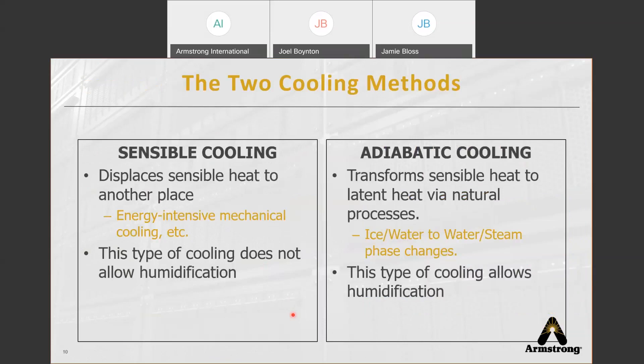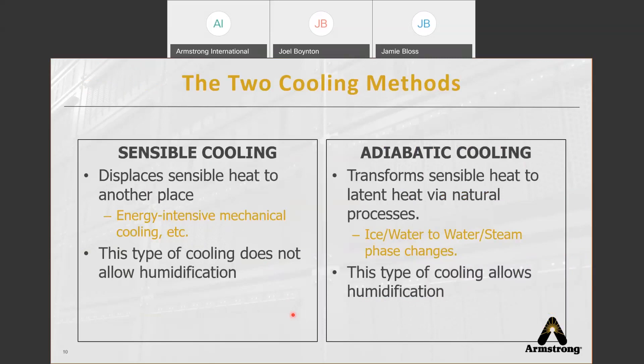That brings us to the two forms of cooling and humidifying in the data center world. These two methods are sensible cooling and adiabatic cooling. Sensible cooling displaces sensible heat to another place — an example is mechanical cooling, which is typically very energy intensive — and this type of cooling does not allow humidification. Contrary to that is adiabatic cooling, which transforms sensible heat to latent heat via natural processes, such as ice to water or water to steam — also known as phase changes. This type of cooling allows for humidification, which is very ideal for data centers since they need both.